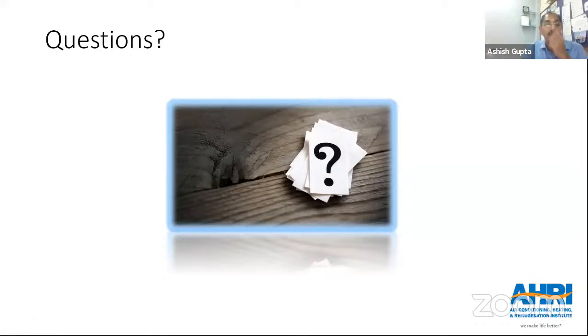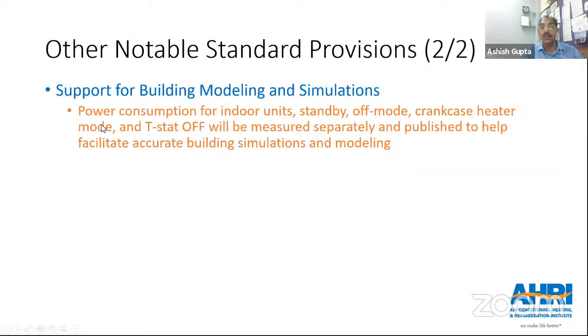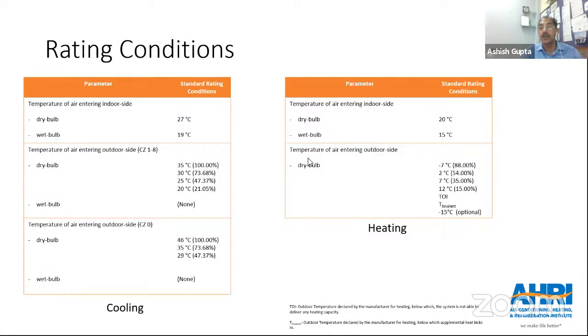One question is: what is the rationale of using 27 degrees centigrade as the indoor dry bulb temperature, when nowhere is it kept as a thermostat set point? Even if various ISO standards use this value, why is no one attempting to get closer to a realistic value? Using a higher indoor temperature gives undue advantage to manufacturers, as the evaporator heat exchanger operates against a higher delta T, thereby increasing the effectiveness of the heat exchanger. Part two: what order of COP and capacity decrease is expected if 27 degrees C is reduced to 24?